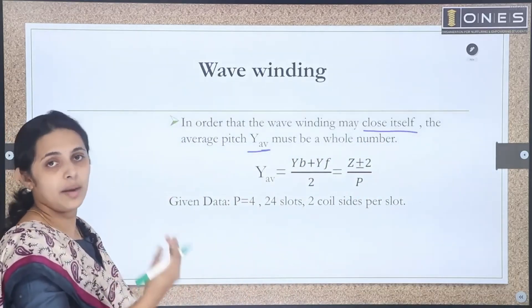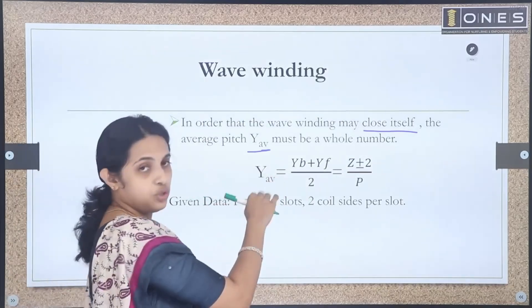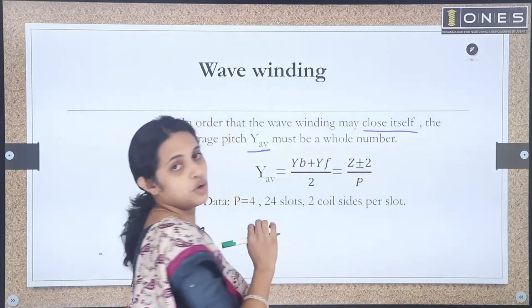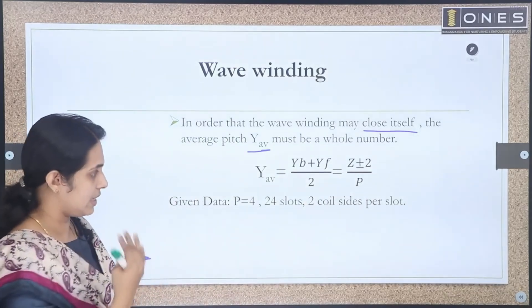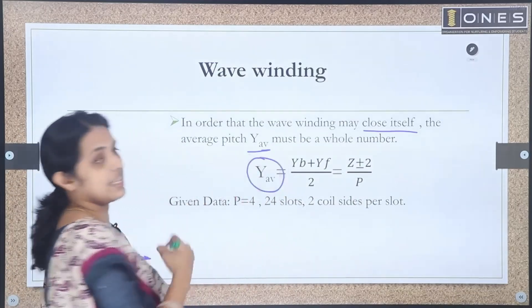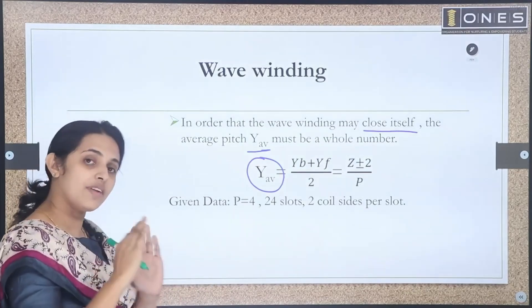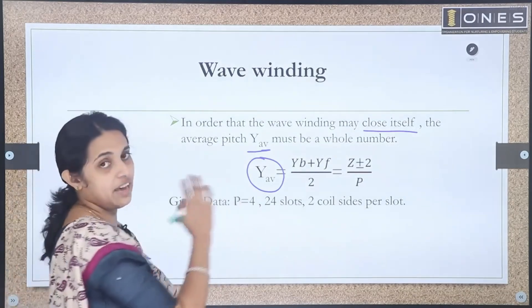In order that the wave winding may close itself, the average pitch must be a whole number. Y_average equals (YB + YF)/2, which equals (Z ± 2) divided by P. This value must be a whole number; a fractional value means wave winding is not possible with that particular number of conductors.